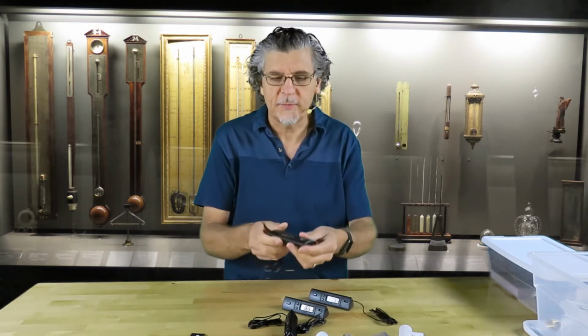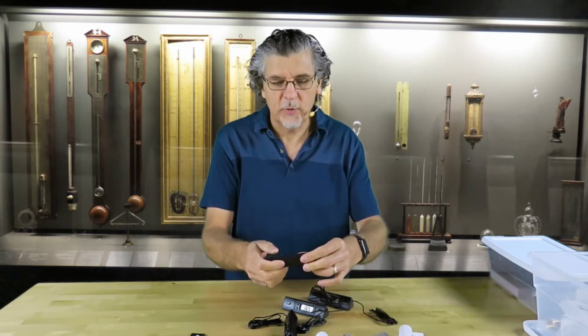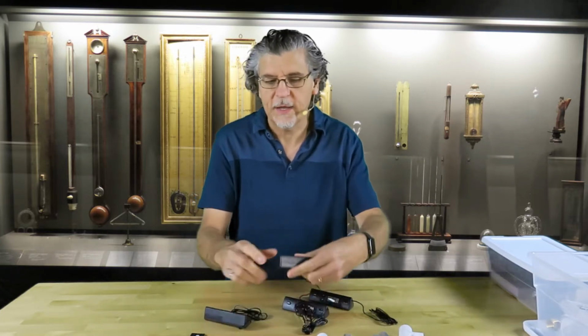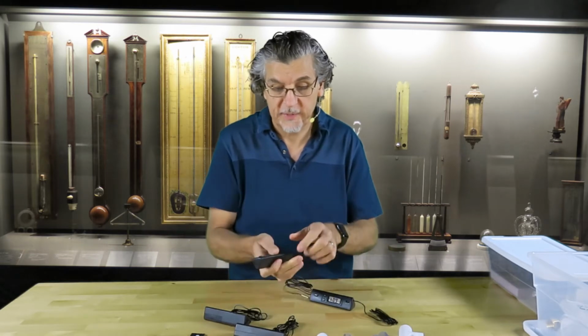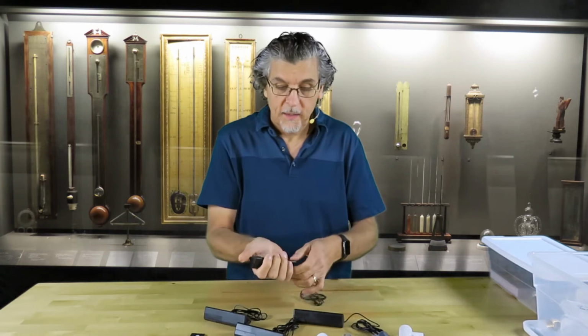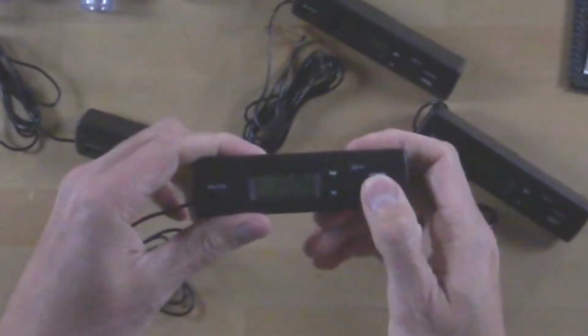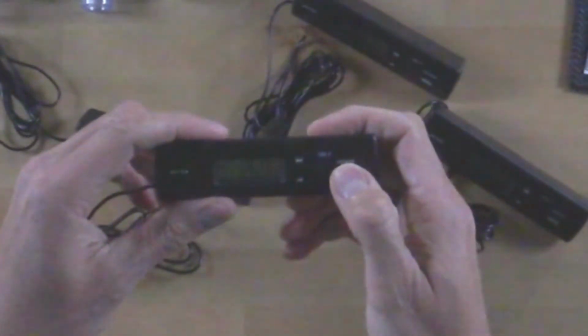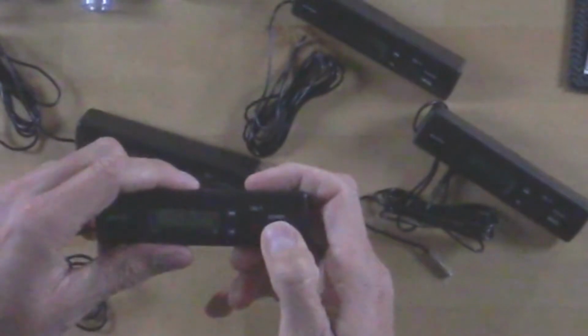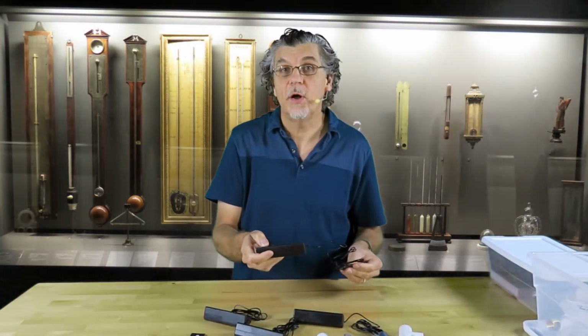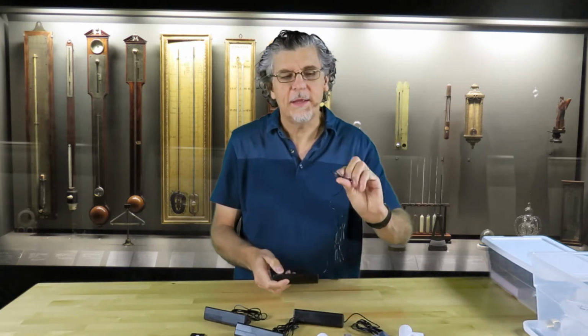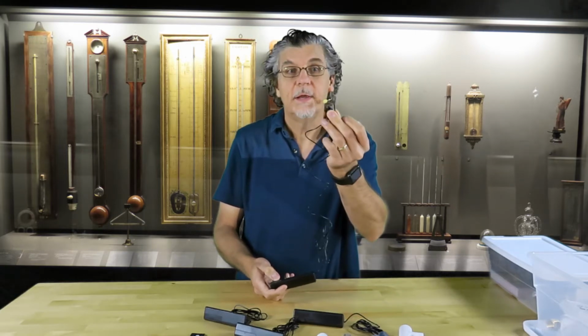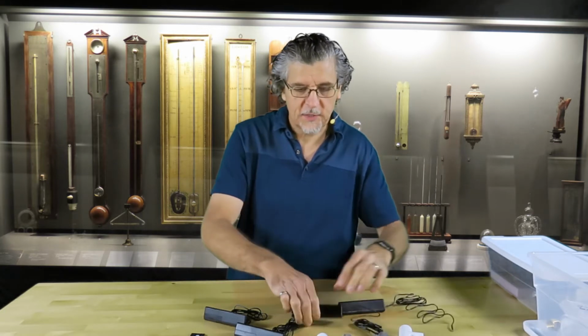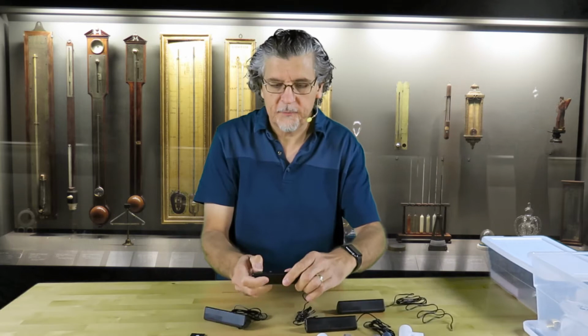A few things to note about the temperature sensors is there is a mode. Well, first of all, you can flip them from degrees C or Fahrenheit. So put them all onto degrees C because we're going to want our measurements in degrees Celsius, not Fahrenheit. So they're all converted, and then there's a mode button on this, and what you can do, the mode button toggles between the clock, time, internal temperature. So there's an internal temperature sensor in the DS1, just like there is with the HTC2s, and there's the out or external temperature sensor. Make sure that they're all on out, because that will then mean that we're monitoring the temperature of the little 4mm NTC probe, and that's what we're going to be doing the calibration with. So they should all be set to out. So I'm going to do that now.